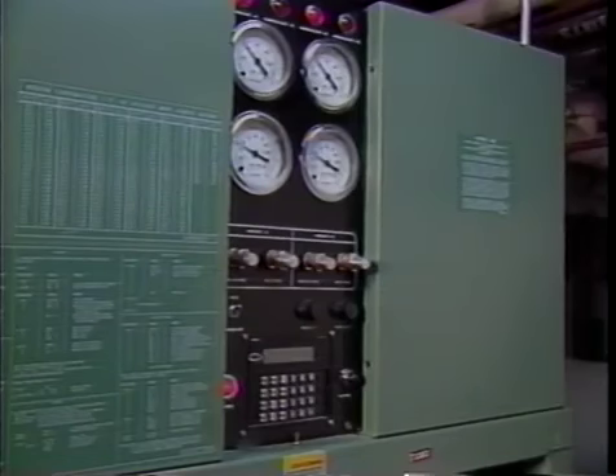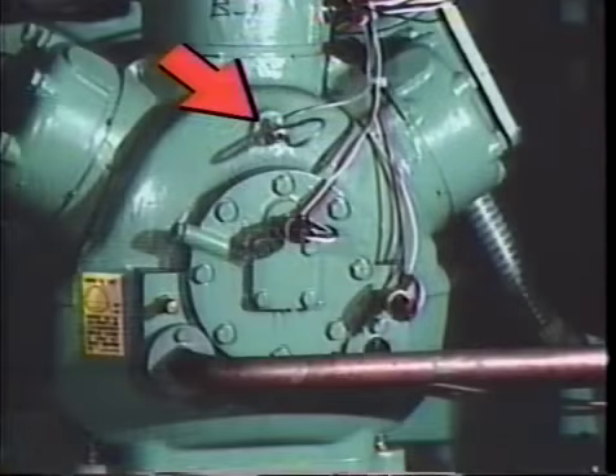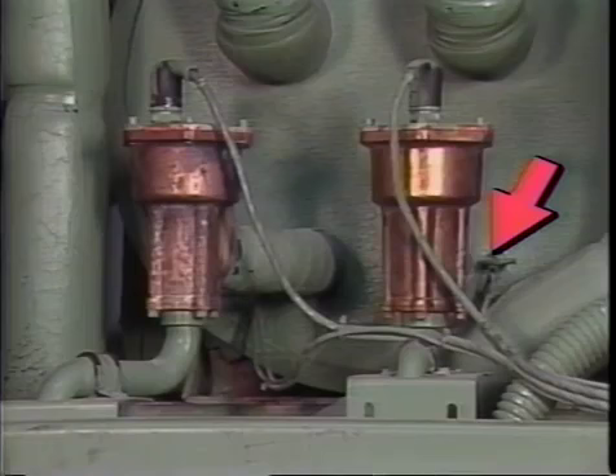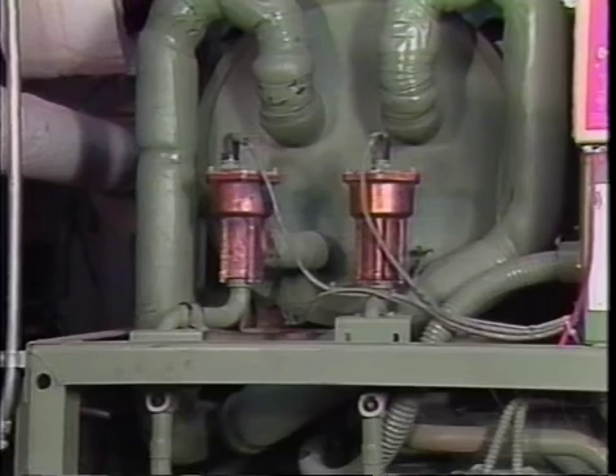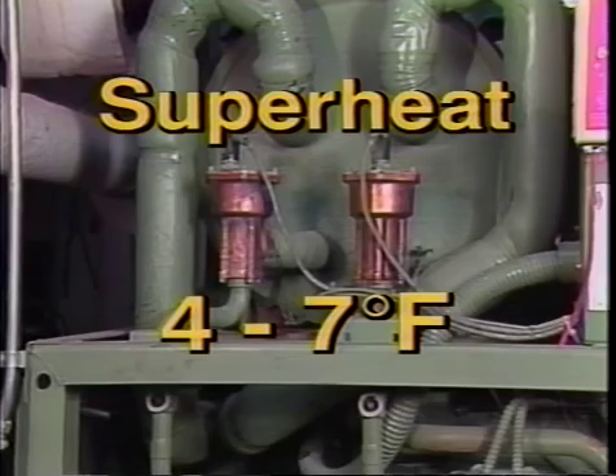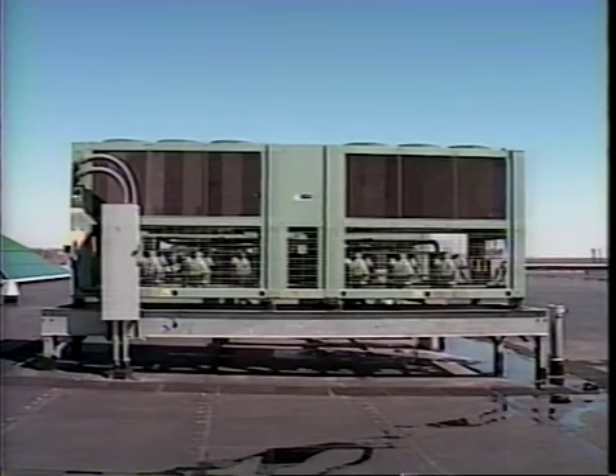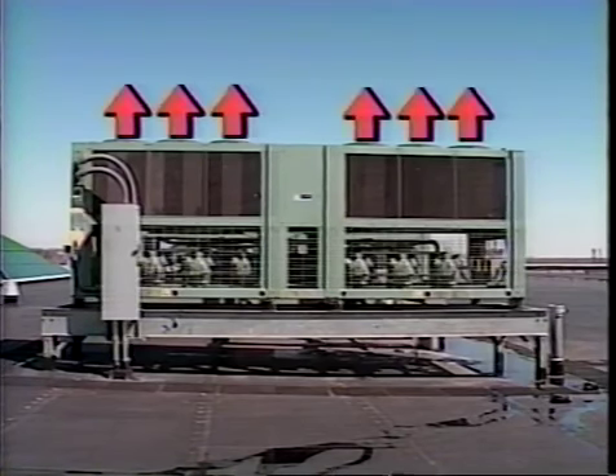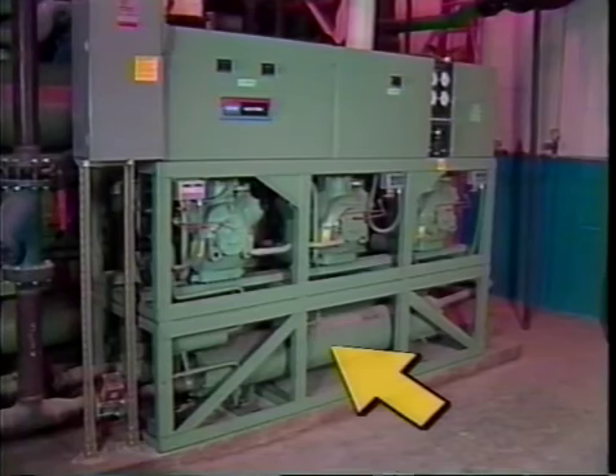More recent designs with electronic controls and sensors placed directly in the compressor and cooler improve capacity by allowing lower superheat leaving the cooler. Superheat of 4 to 7 degrees Fahrenheit is typical on these newer chillers using electronic expansion valves. The heat flow in the condenser is from the hot refrigerant gas to either air flowing over the tubes in air-cooled condensers or water flowing through the tubes in water-cooled condensers.